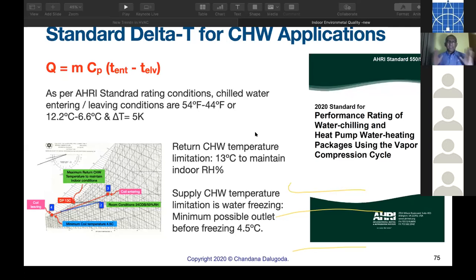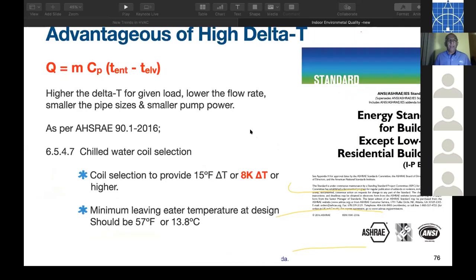Now, this is the standard. This is what we discussed a little while ago. So, return chill water temperature limitation is 13 degrees to maintain good RH. Supply chill water temperature is limited by water freezing. Minimum is 4.5. So we are working between that. So AHRI specified 7 and 12. That is the normal standard delta T. But ASHRAE, after 2016, is now specifying high delta T applications for chill water coils. They say chill water coil selection should provide 15 Fahrenheit delta T or 8K. How to get 8K now?